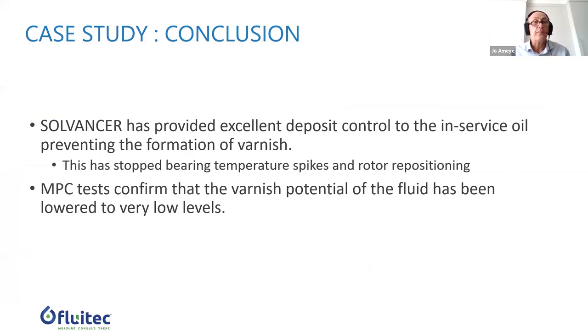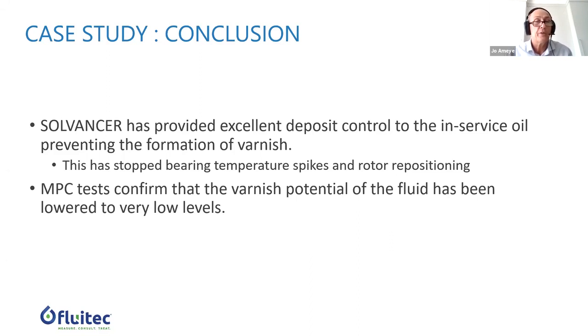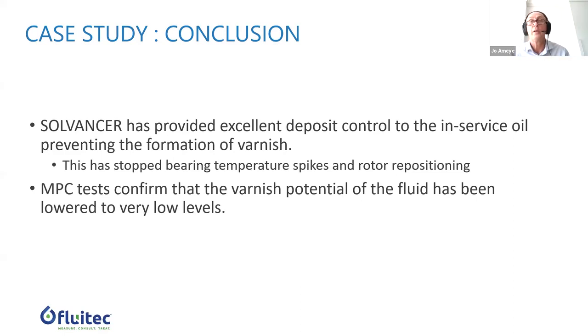This proves that the oil film is again in a 100% hydrodynamic normal condition, helping to cool down the surface. In conclusion: Solvancer, in combination with contamination control, will help you prevent the formation of varnish and stop bearing temperature spikes. Last but not least, focus on oil analysis — make sure you monitor the MPC test, as it will help you detect early warning signals of possible deposits.